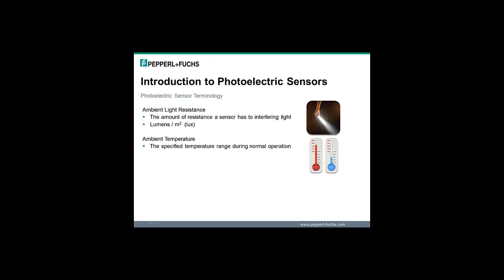Measured in lumens per square meter or lux, ambient light resistance is a specification denoting the sensor's ability to ignore light at the receiver which did not originate from the transmitter. A high resistance to ambient light is critical. Without it, nearly any source of light could interfere with the operation of the sensor — including sunlight, fluorescent lighting, incandescent lighting, as well as other photoelectric sensors in the area.